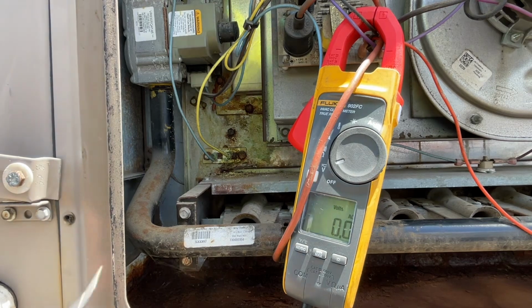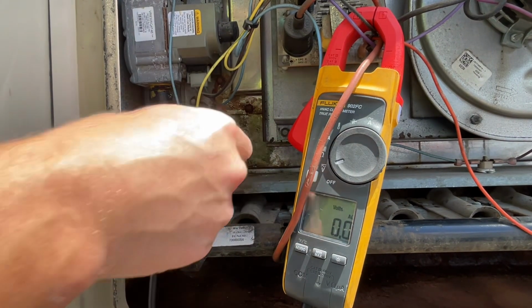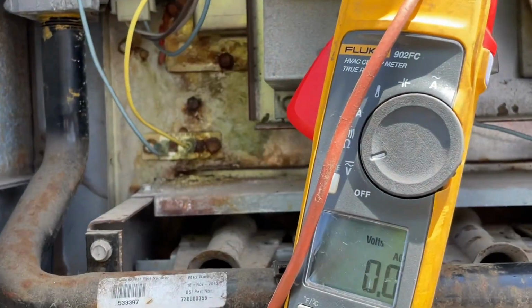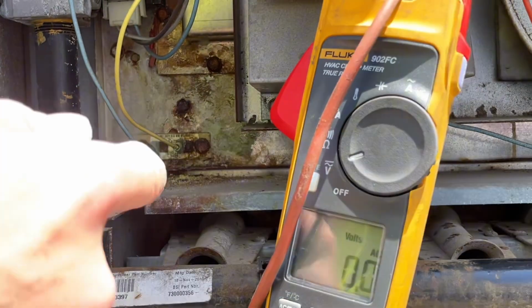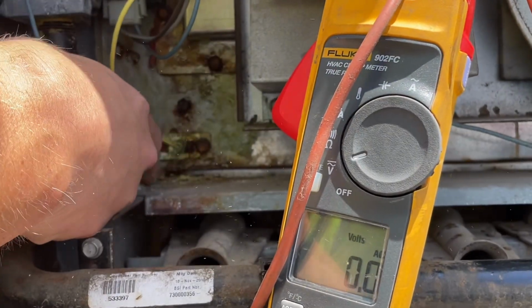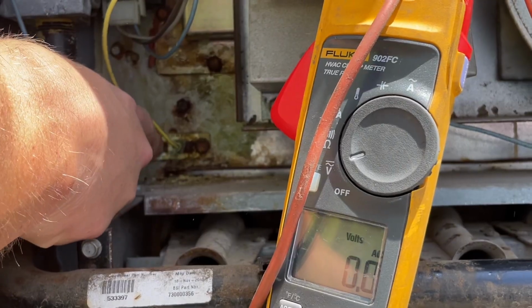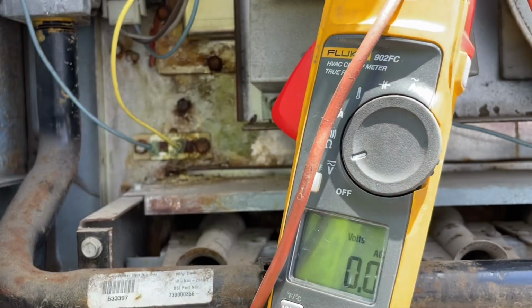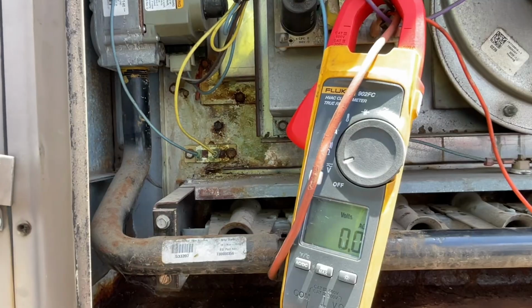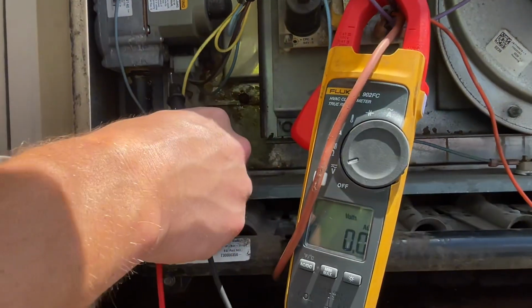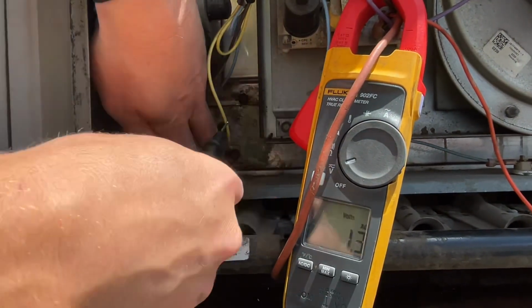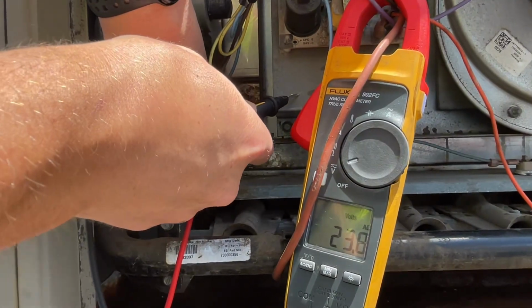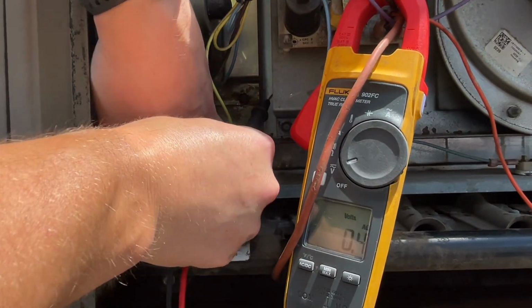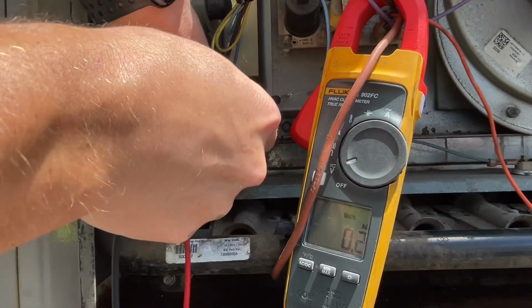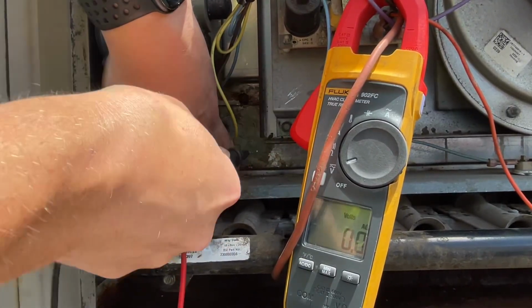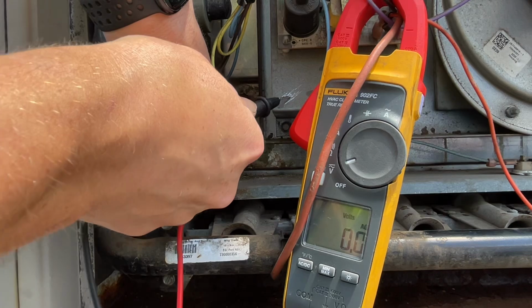Okay, we located our limit switch. It's right here, and it looks awful. Extremely rusty. Can you guys see that? Right there. Both these wires are just a 24 volt through the safety, but let's get a reading with our meter, see if we even can, because these are in awful shape. So we'll go on one side of our pin here to ground. We have 23, 26 volts there. Let's try our other side. We have nothing there.